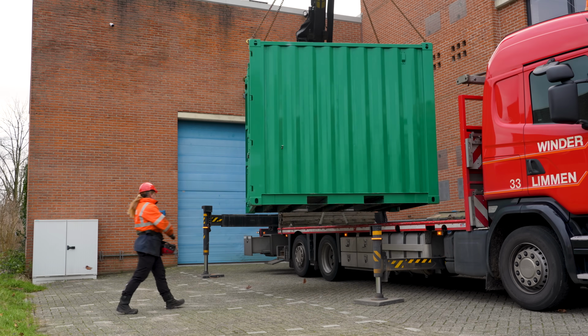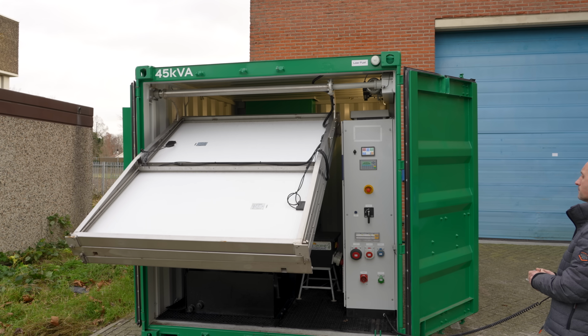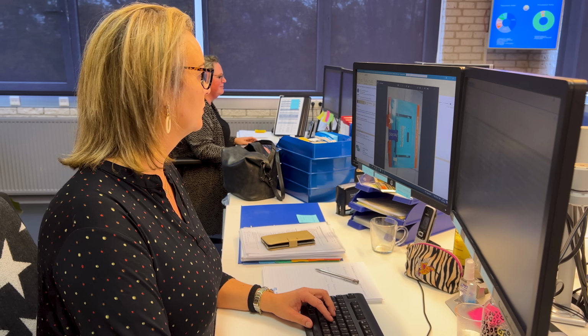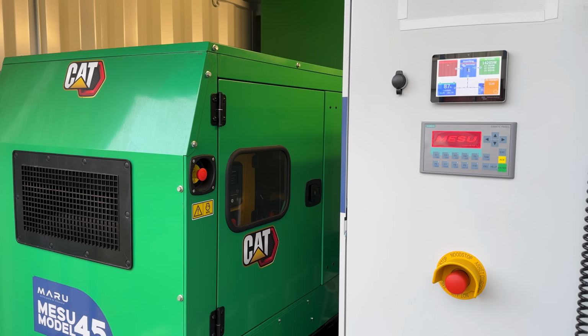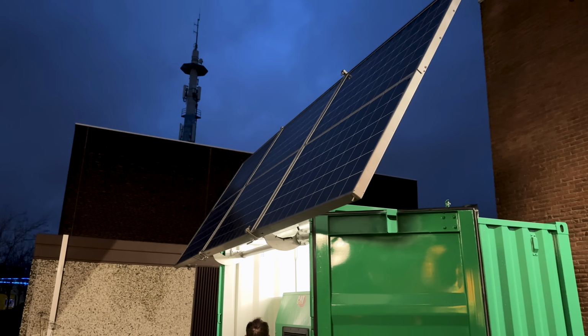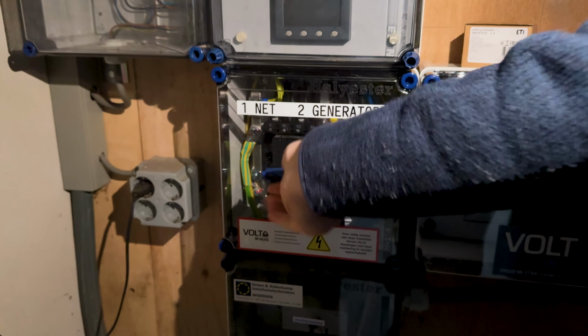At the start of 2024, several areas around the Victron Energy headquarters building in Almere, Netherlands, had their power disconnected so the electricity transformers and distribution huts could receive maintenance. With computer equipment and offices required to maintain electricity, we ourselves turned to green generators. A new generator input was created in the power plant room of the building. On the morning of the power maintenance cut-off, before the grid disconnected, the generator was plugged into the input, turned on, and the site was switched from grid to generator.